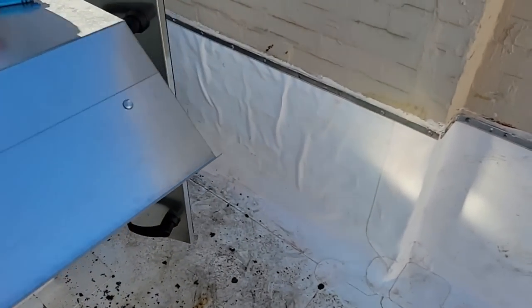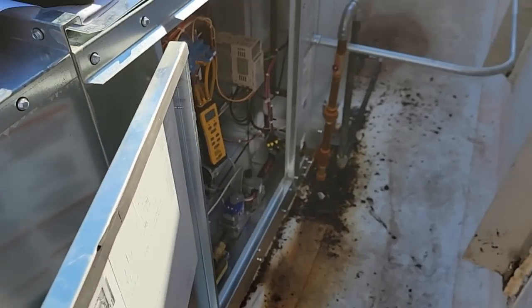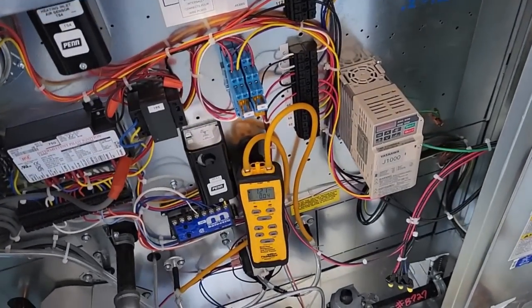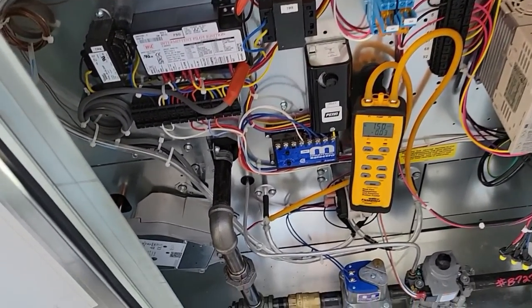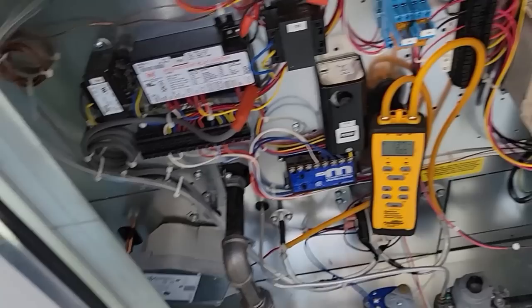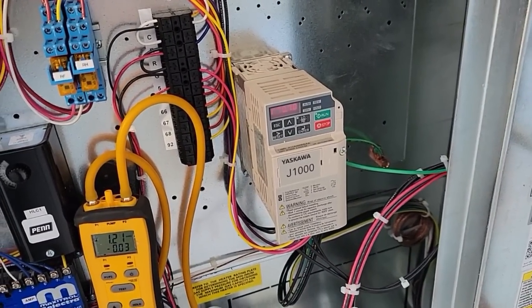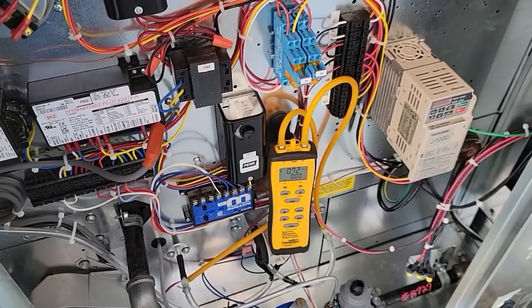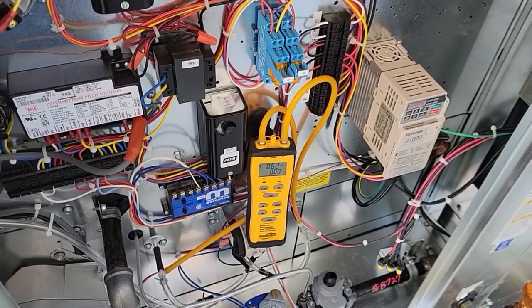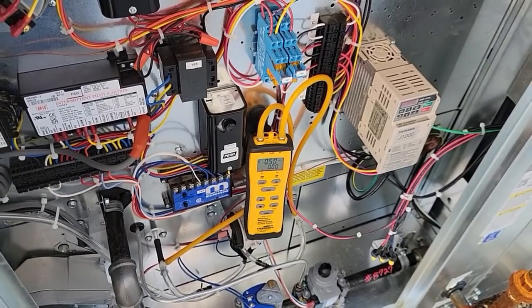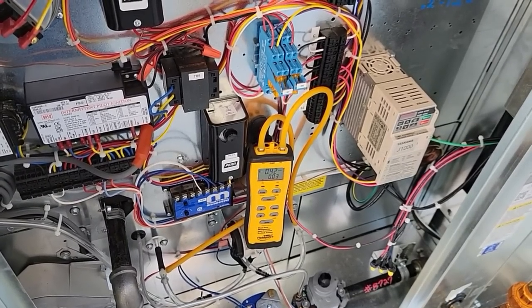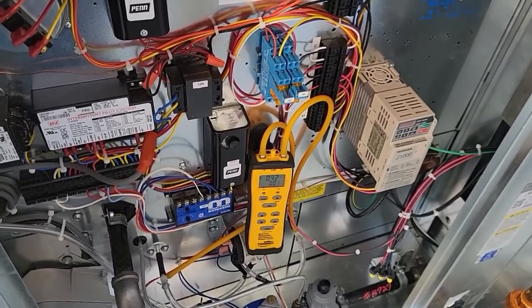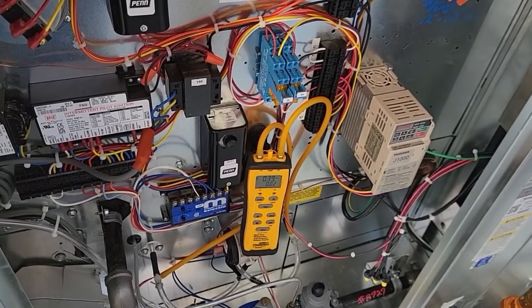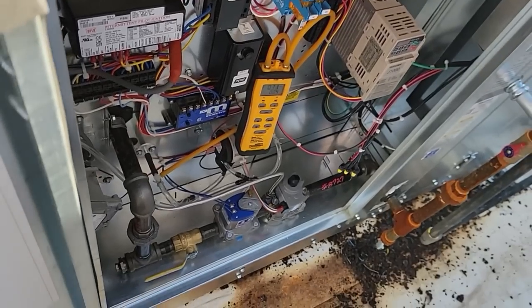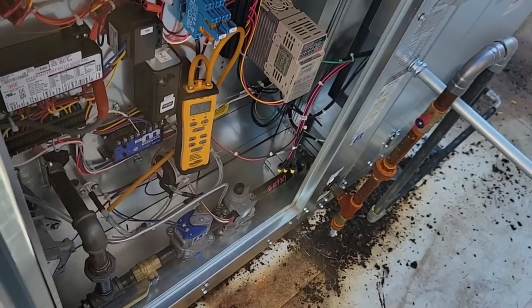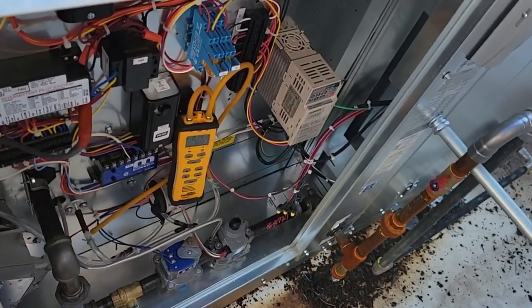They are running the test right now to make sure that when the fire alarm trips, this thing shuts down, which the damper just shut, and we're waiting. Yep, there it goes. You can hear the fan dropping. Good deal. Theoretically, they don't really care whether the machinery works as far as actually producing heat. They want to make sure that for fire reasons it, yep, there it reverses. They must have untripped it. Good deal. Now we can probably set it up.